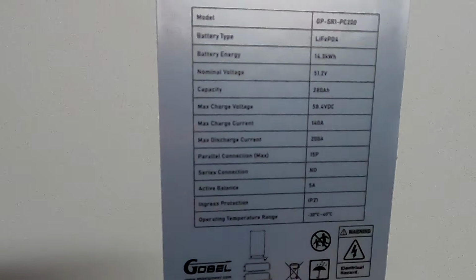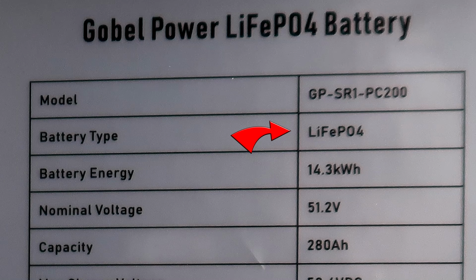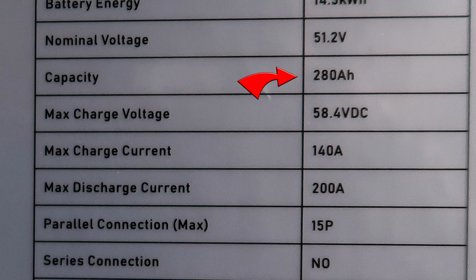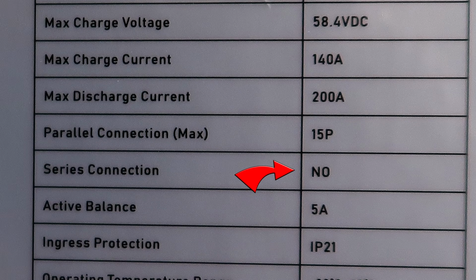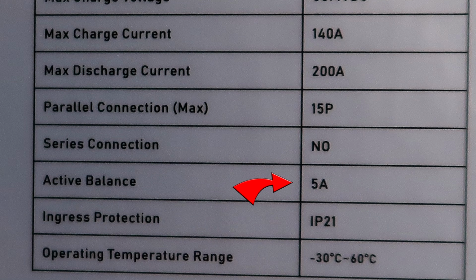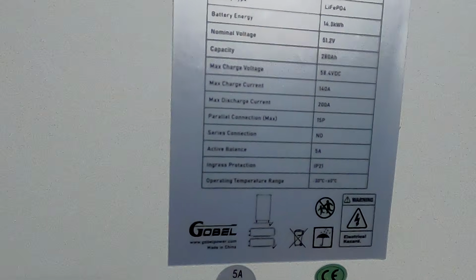Let's have a look at the sticker. Battery type: lithium iron phosphate, 14.3 kilowatt hours, 51.2 volts, 280 ampere hours. Max charge voltage 58.4 volts, maximum charge current 140 amps, discharge current 200 amps. We can put 15 of them in parallel, no series connection of these batteries. We've got a 5 amp active balancer in this battery.